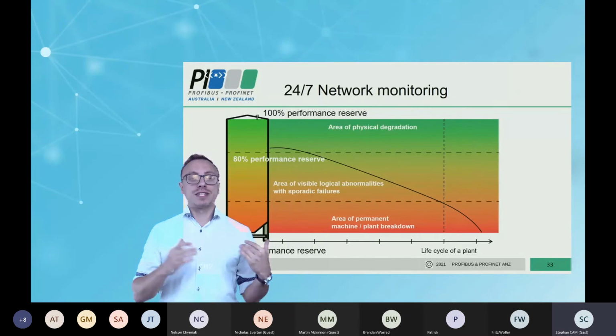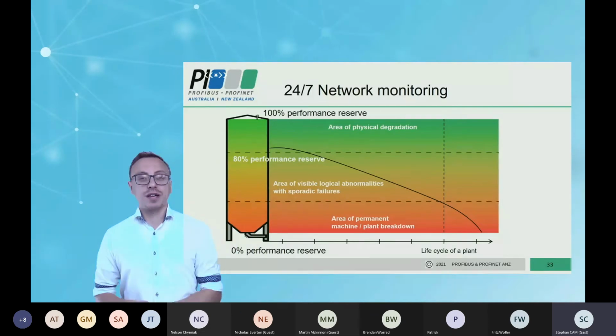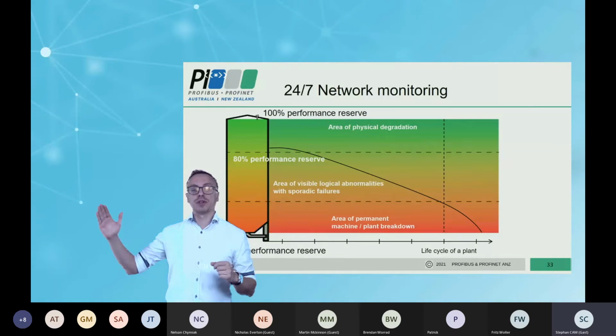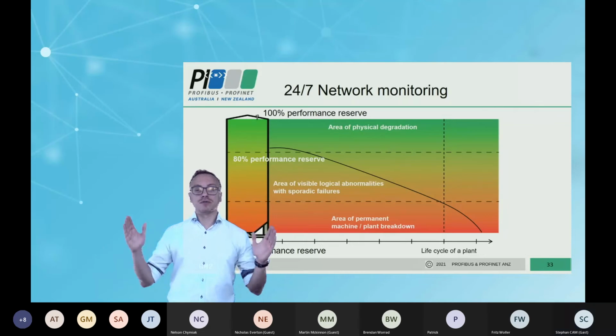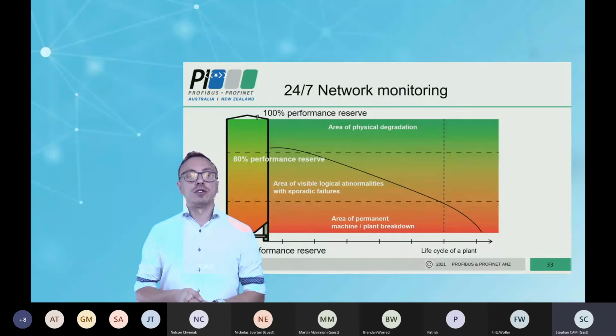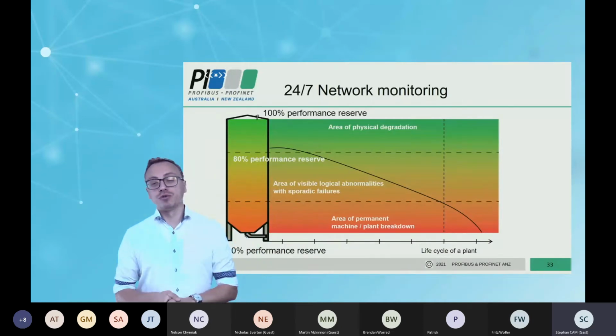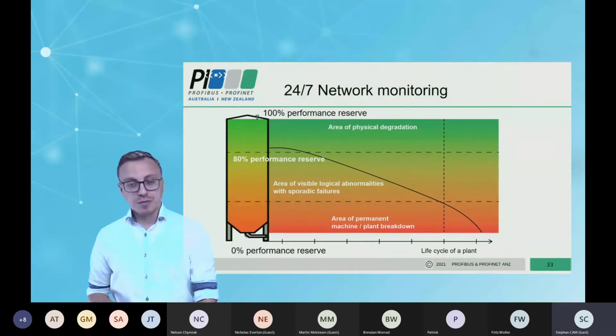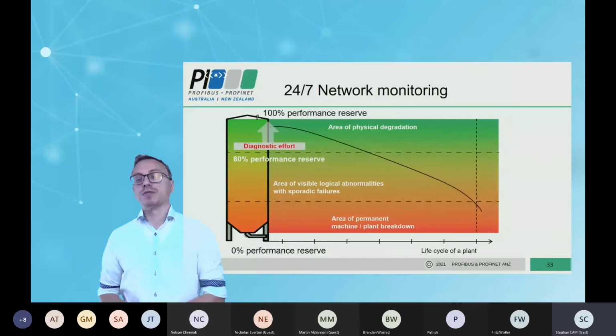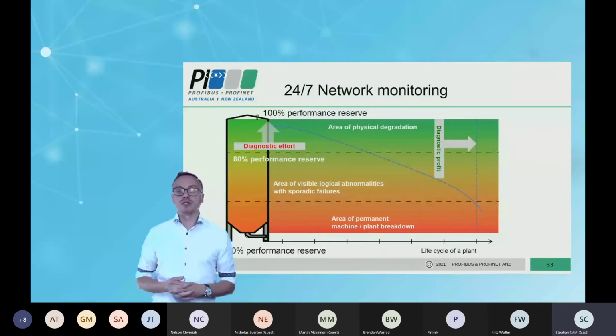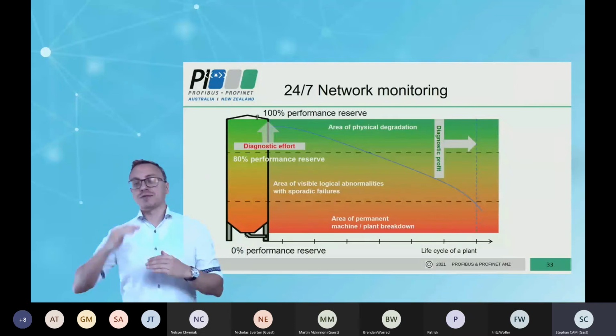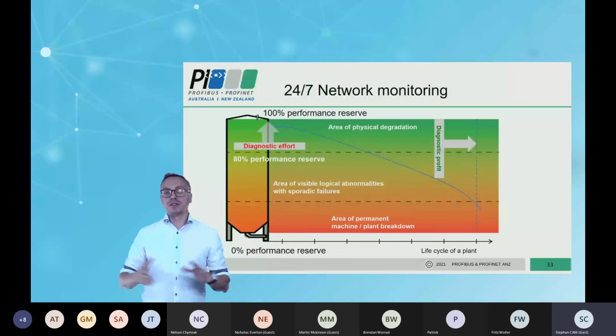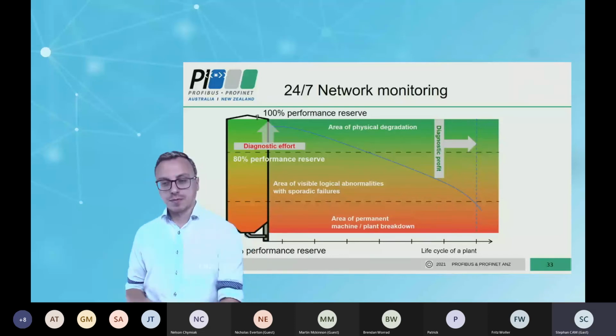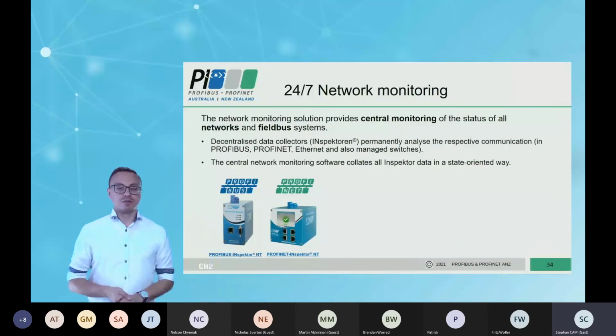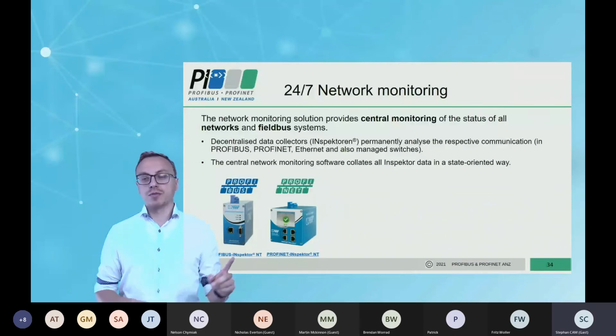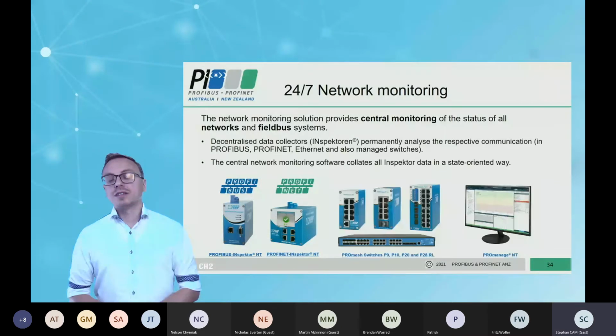For example, in our statistics, we found that if you work with the PROFINET inspector, normally you have 2 months before you get a stop of your plant. So the inspector gives you 2 months to look around your plant, think about the issue, and maybe do the troubleshooting before you get an immediate stop of the plant. And if you act and the inspector or other measurement tools show you your diagnostic effort, you can increase your life cycle or the health of the plant. So you can do it very easily with measurement tools like the inspectors. We have these inspectors for PROFINET and Profibus as well. And you can do it with managed switches.